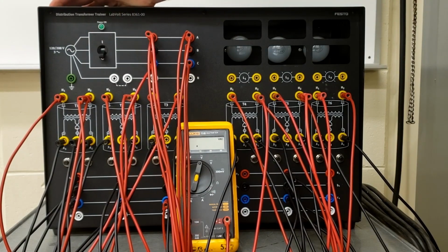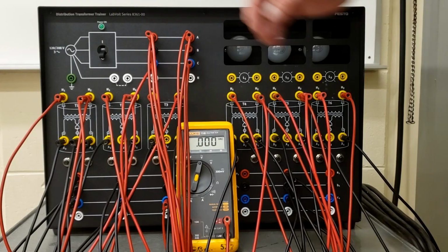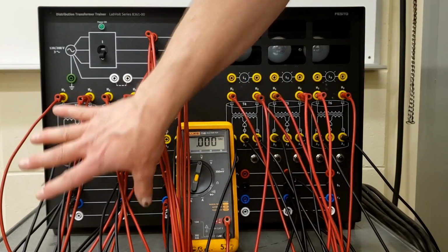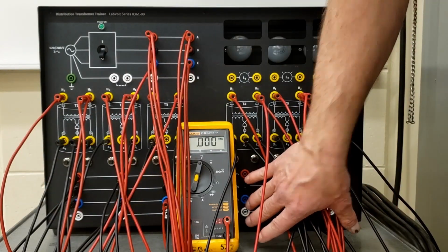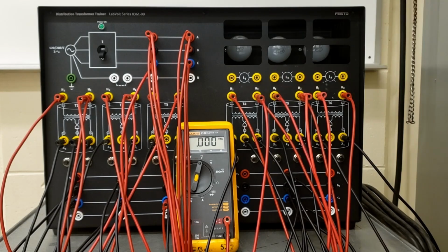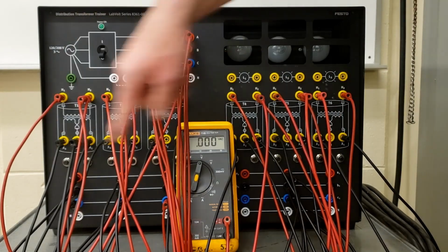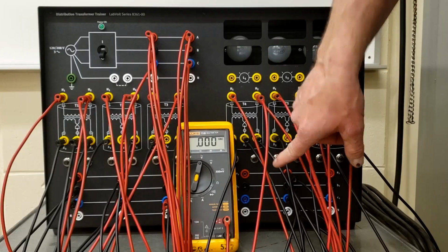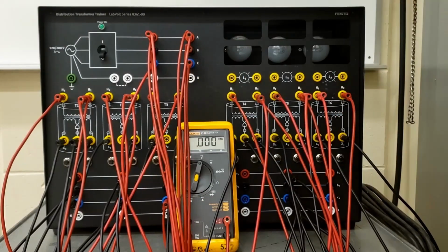Beautiful, so that makes sense. We have 240 volts between any of the lines on this bus on the secondary side of our second bank of transformers. Then on A phase between either one, 0 volts difference, B phase 0 volts difference, C phase 0 volts difference.